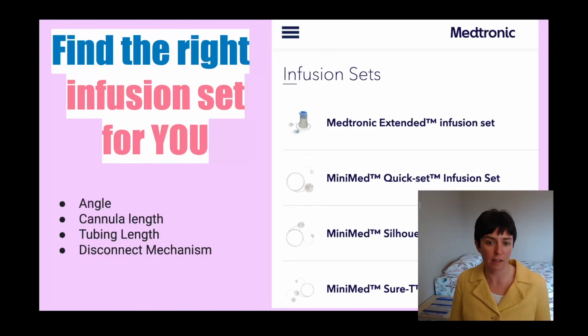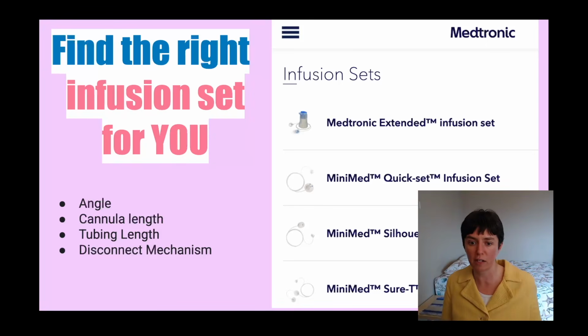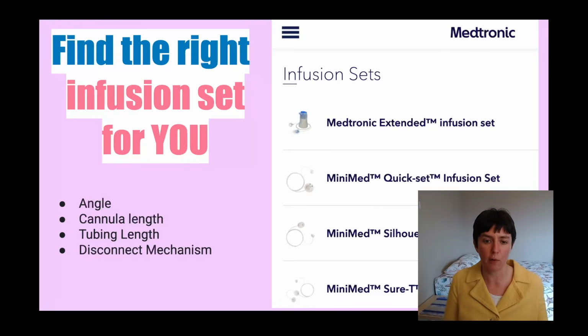I had a dexterity issue - the quick set, you have to turn it to disconnect. What's great about the insulin pump is you can disconnect from it, for example when taking a shower, I always disconnect. But I had dexterity issues, and the quick set was difficult for me to disconnect from. So I've since switched to the Medtronic extended infusion set, which is not only 7 days long, but also has an easier disconnect mechanism.